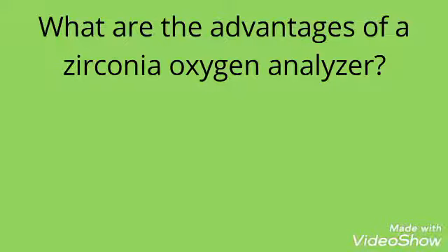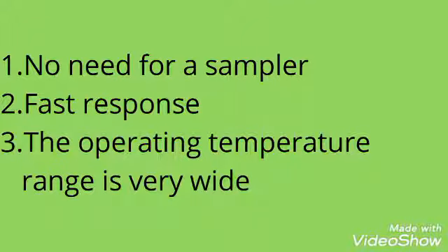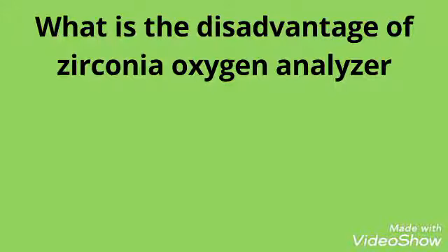What are the advantages of the zirconia oxygen analyzer? Here we will discuss its advantages. No need for a sampler, fast response, and the operating temperature range is very wide. So these are all the advantages.